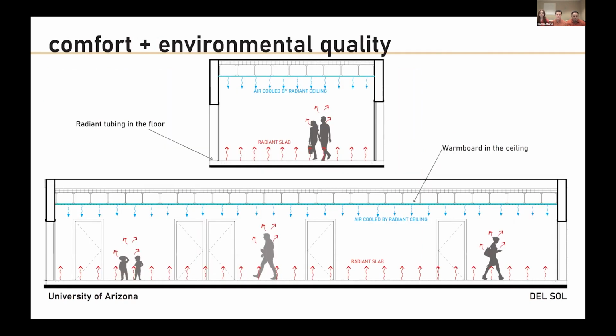A primary way of maintaining occupant comfort in Tucson's long cooling seasons is to remove heat from the people, objects, and surfaces in the space using radiant cooling. With our super efficient building envelope, all we need is 60-degree water circulated in radiant tubes embedded in the entire ceiling to maintain comfort.